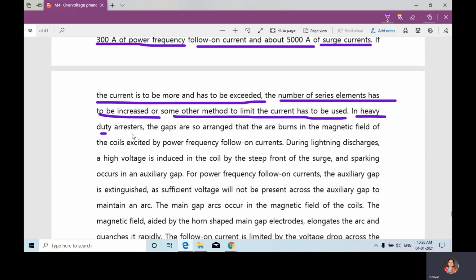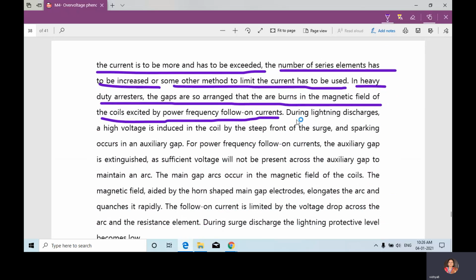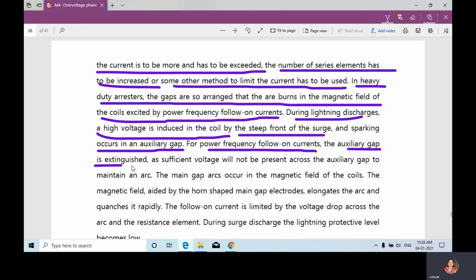Next, in heavy duty arresters, the gaps are so arranged that the arc burns in the magnetic field of the coils excited by power frequency follow-on currents. During lightning discharge, a high voltage is induced in the coil by the steep front of the surge, and sparking occurs in the auxiliary gap. For power frequency follow-on currents, the auxiliary gap is extinguished, as a sufficient voltage will not be present across the auxiliary gap to maintain an arc.